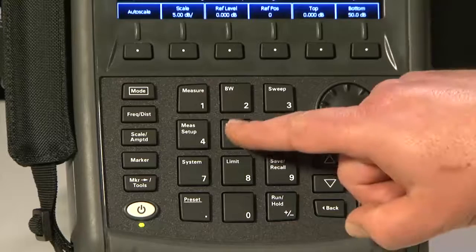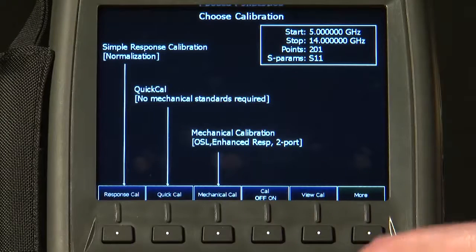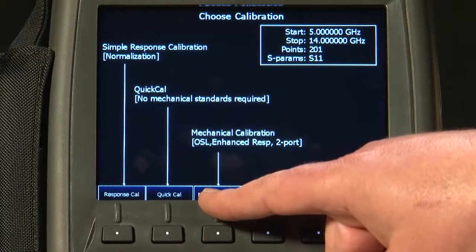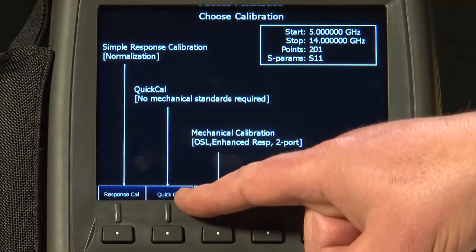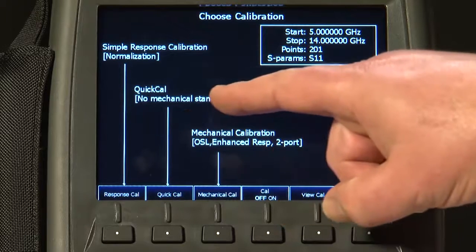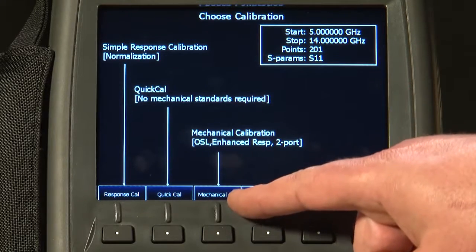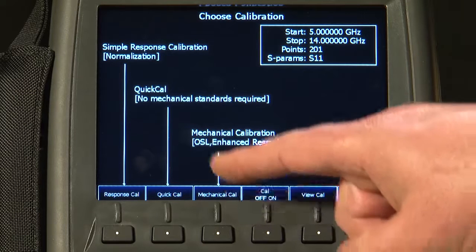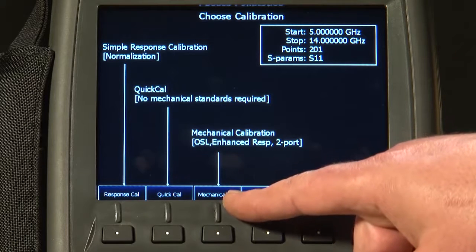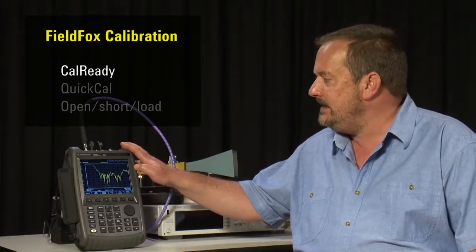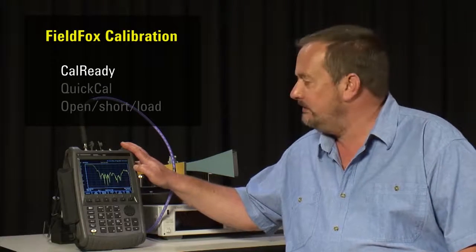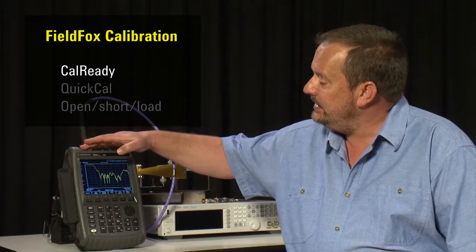Well, if I press the CAL button, you will see we have a number of options for calibration: a simple response CAL, a quick CAL which I will talk about in a moment, which allows us to do a calibration with no mechanical standards required, or of course, we can do a full open, short load calibration if we wish. But every FieldFox is pre-calibrated when it leaves the Agilent factory at this reference point here.